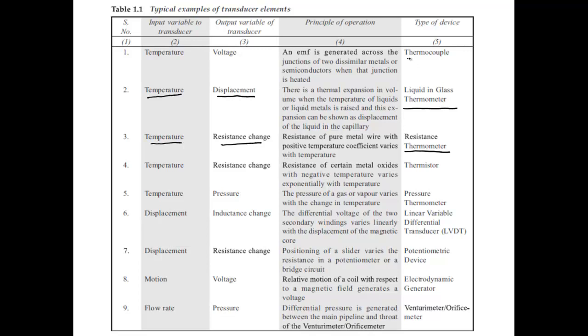For a thermocouple, the principle is that an EMF is generated across junctions of two dissimilar metals or semiconductors when that junction is heated — input is temperature, output is voltage. For a thermistor, similarly temperature is the input. For a pressure thermometer, temperature is the input but pressure is the output — the principle being that the pressure of a gas or vapor varies with change in temperature.